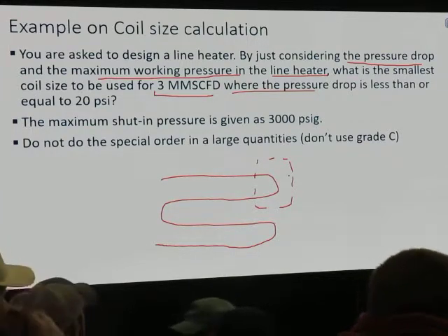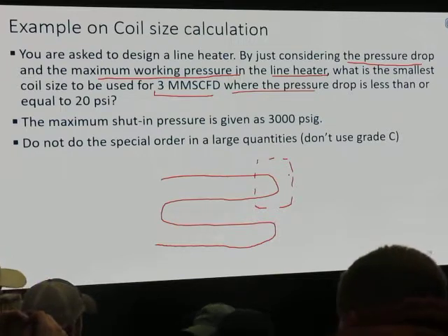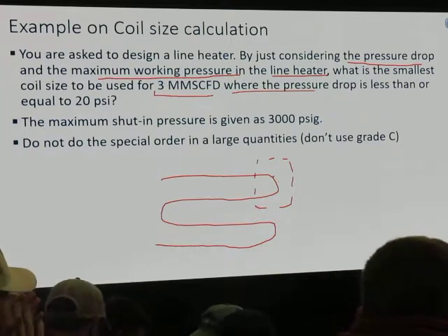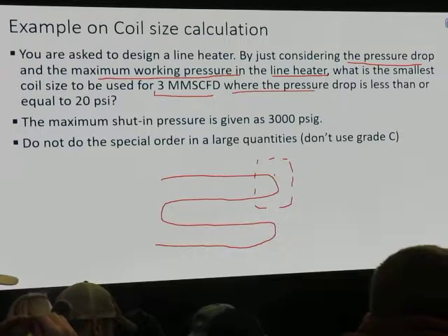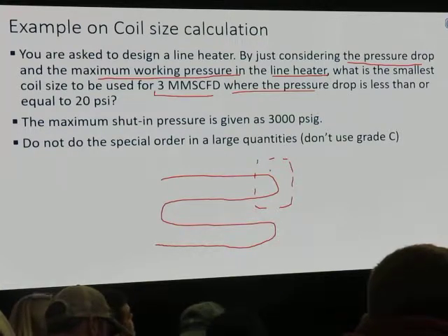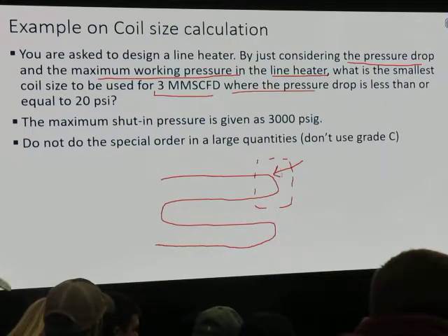The pipe that we bought just comes as is. We tell them this part number, they send it, and they put everything needed in there already. Okay, so provided that we calculate the erosional velocity. Of course the turn, they engineered it already, but they don't really tell us what's in there, whether they make it a little bit bigger over there. They say if we use the right erosional velocity and we are below it, we don't have to worry about anything. This turn part, very obvious, I think it is more susceptible to erosion. More questions? Let's take a look at how we do it.